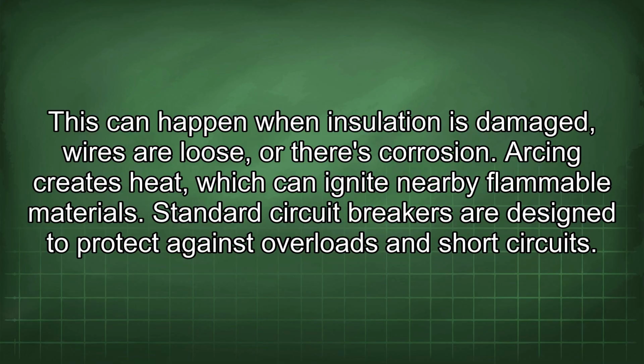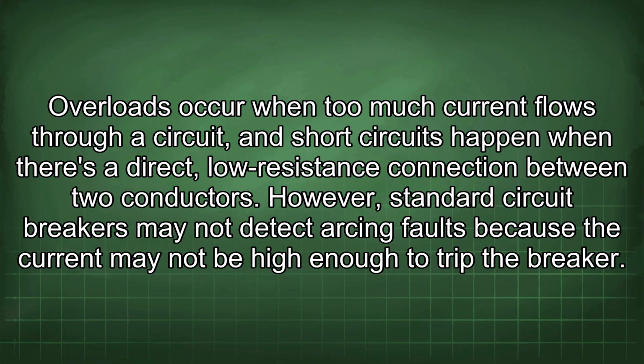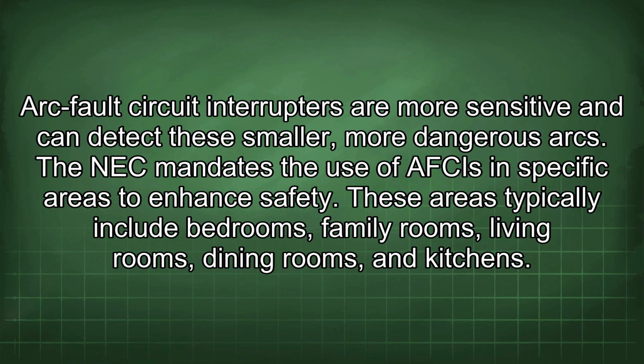Standard circuit breakers are designed to protect against overloads and short circuits. Overloads occur when too much current flows through a circuit, and short circuits happen when there's a direct low-resistance connection between two conductors. However, standard circuit breakers may not detect arcing faults because the current may not be high enough to trip the breaker. Arc fault circuit interrupters are more sensitive and can detect these smaller, more dangerous arcs.